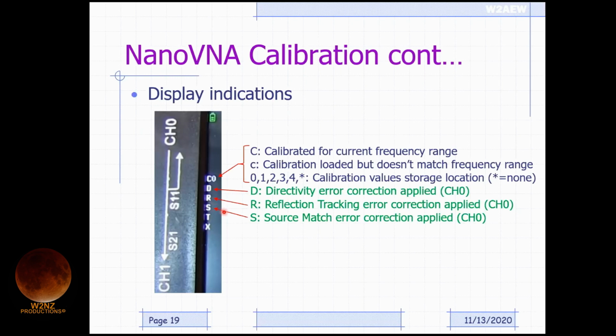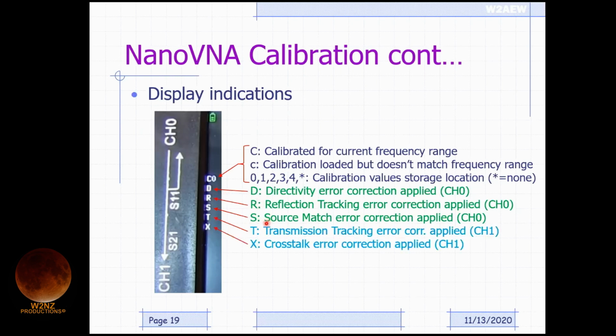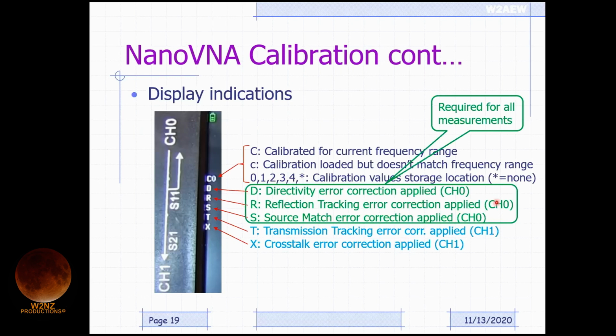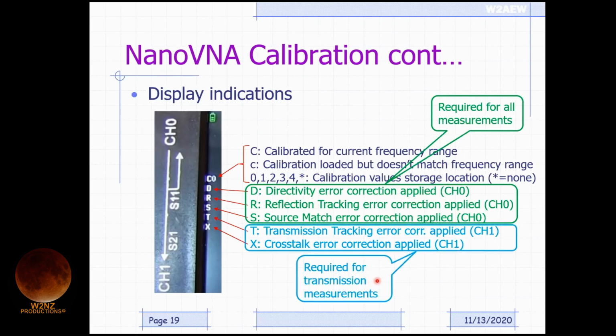The D, R, and S mean that the directivity, reflection tracking, and source match error corrections have been applied. These are all applied on channel 0 as part of the calibration process. So that tells you that you've properly calibrated out those systematic errors. Then the transmission and crosstalk corrections have been applied, which are for 2-port transmission measurements: the transmission tracking error and the crosstalk, right? This first set is needed generally for all measurements, SWR measurements, return loss measurements, things like that. This last set is really only needed when you're making transmission measurements through a device, like a filter. So you don't have to do that portion of the calibration if you're only measuring reflection properties, like sweeping an antenna, for example.